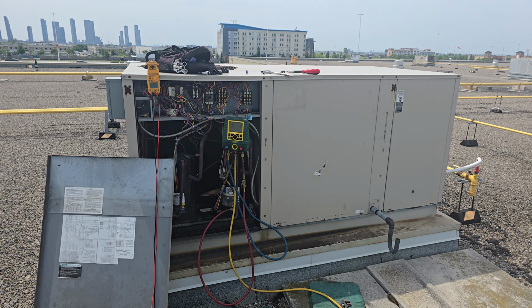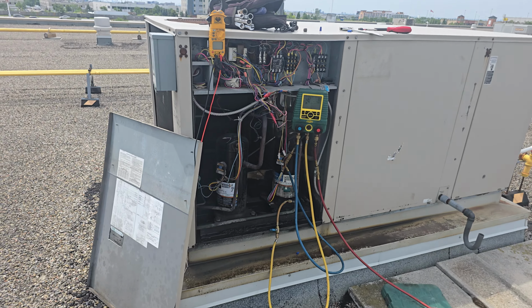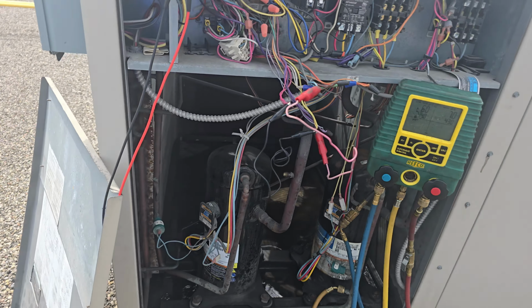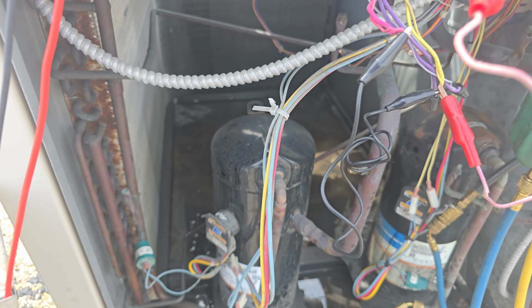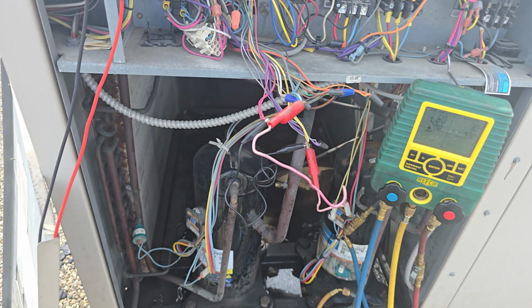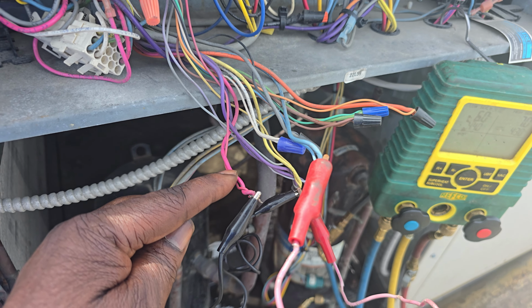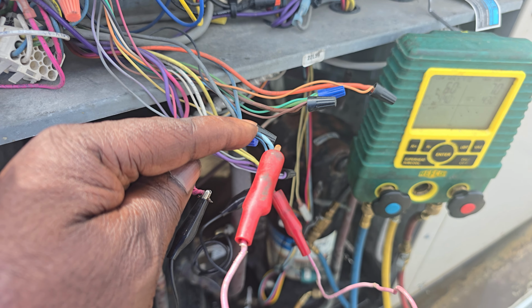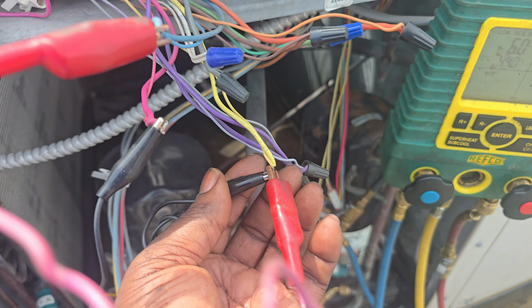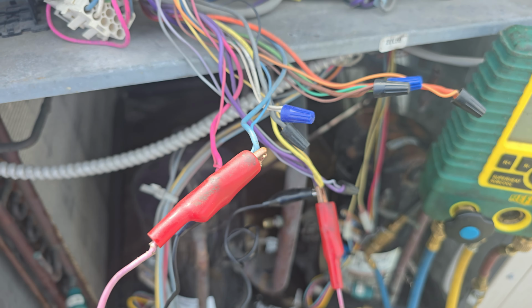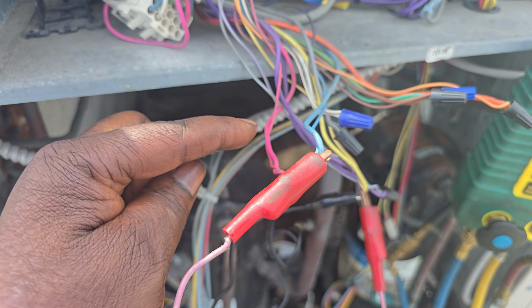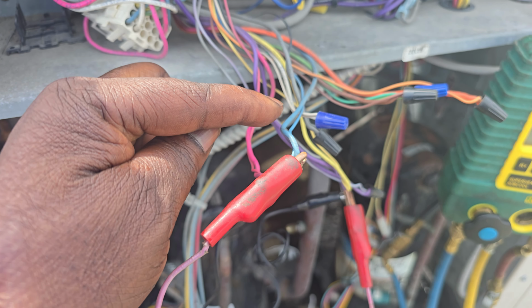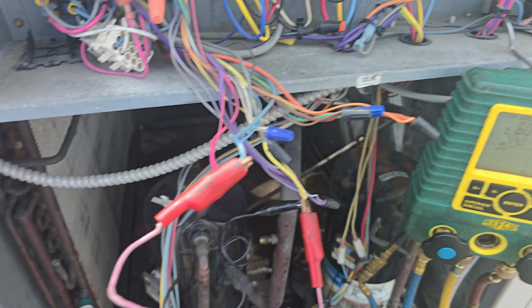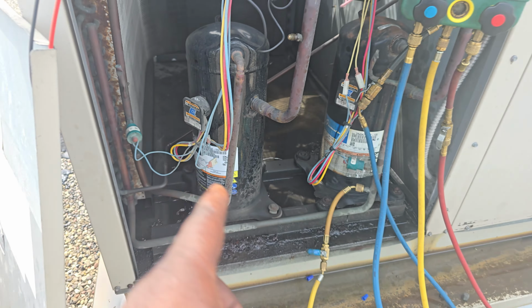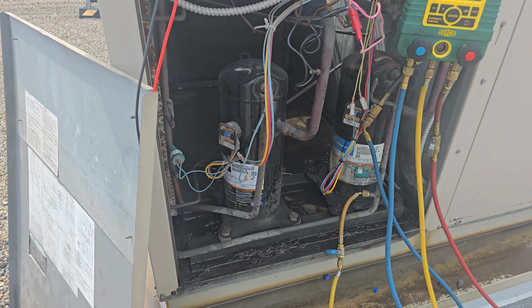Okay, so just to confirm, my compressor number 2 is okay. What I'm going to do here: this is my 24 volt, here's my compressor number 2, and here's my compressor number 1, which is yellow. I put a jumper between the 24 volt, compressor 1 and compressor 2 to call in compressor number 2 and 1. I'm going to try that for a few seconds.